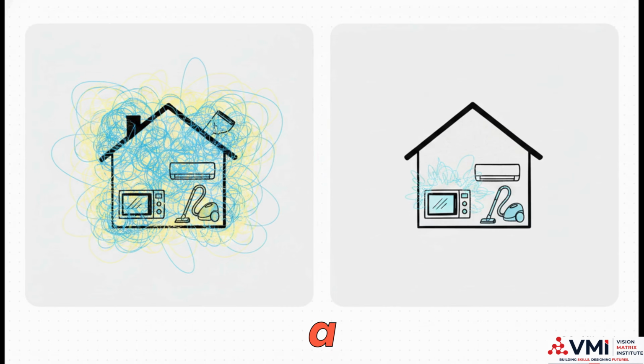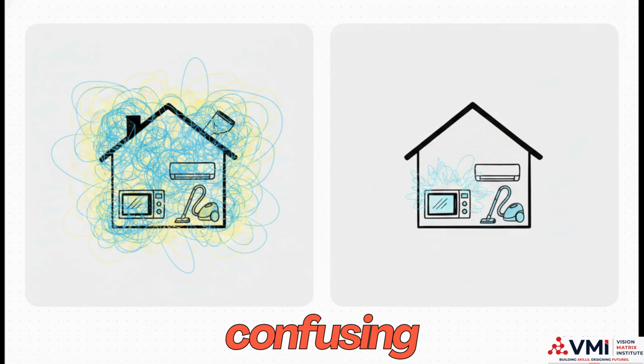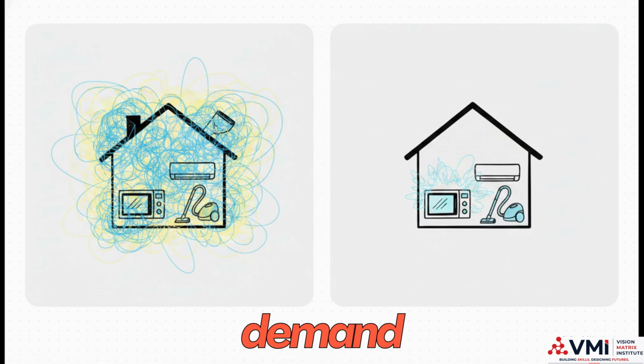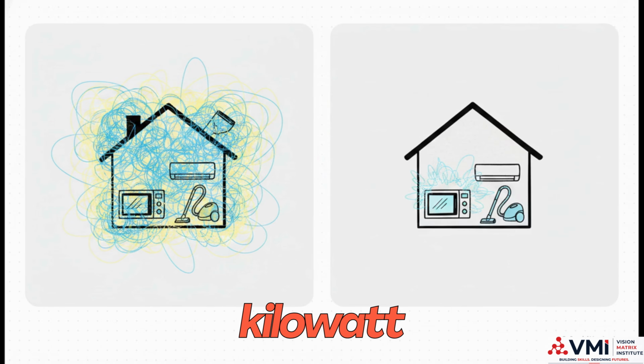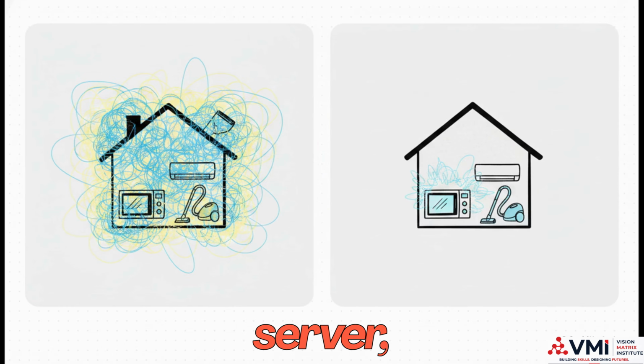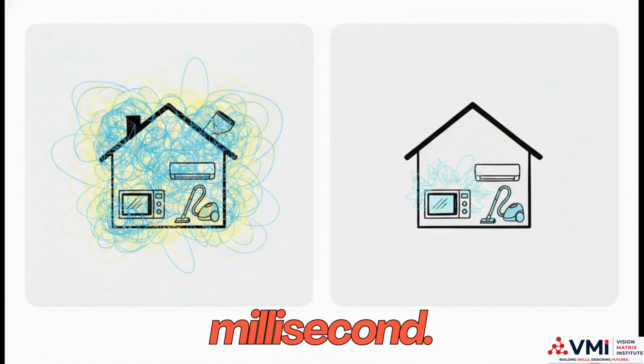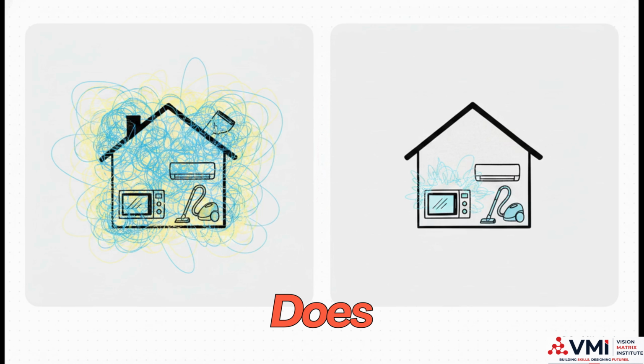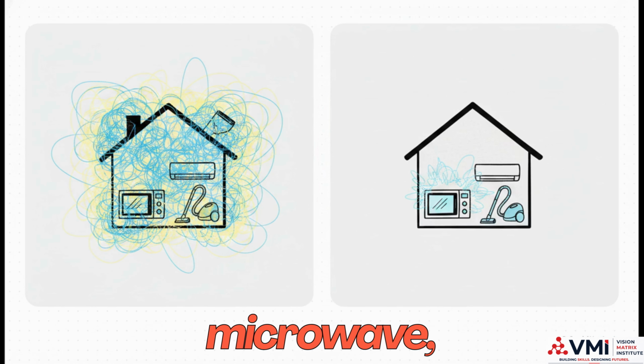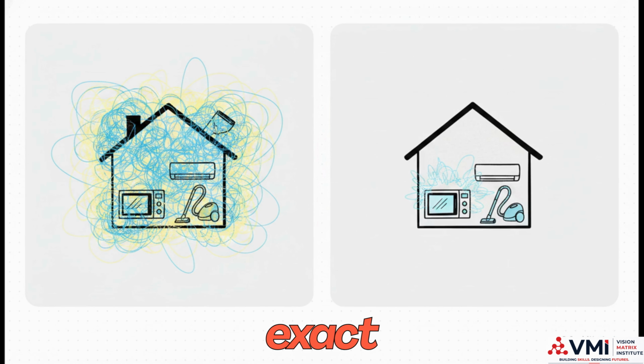Now, the biggest mistake a rookie engineer can make here is confusing connected kilowatt with demand kilowatt. Connected kilowatt assumes that every single server, light bulb, and cooling fan is running at 100% capacity at the exact same millisecond. But think about your own neighborhood. Does every single house run their microwave, their air conditioner, and their vacuum cleaner at the exact same moment?